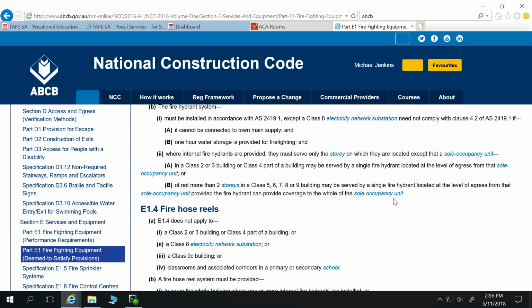May be served by a single fire hydrant. We've got that option, but that only works if we've got an open stairway between either one. If we've got a fire isolated stairway, well then that doesn't work. Yeah. So in short, what that's telling us is we need to have a fire hydrant on every level.